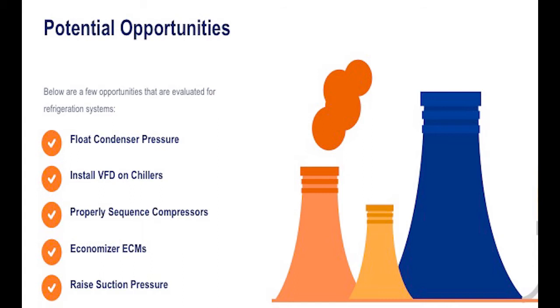Some of these were mentioned before, but we'll be looking at both floating the condenser pressure on your refrigeration system, as well as raising the suction pressure. All that has to do with reducing that lift on your compressors so you're putting less work on them.